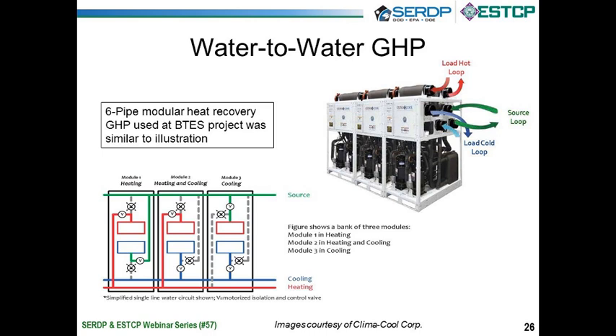This is LogCom, three-star general, 800 employees. We don't want it to go down. We don't need but about three or four of those heat pumps at any given time, but we need to keep that facility up and running. We have hot water that connects to it. We did change the hot water from a ridiculous 160 degrees down to 110 so we could do free heat.